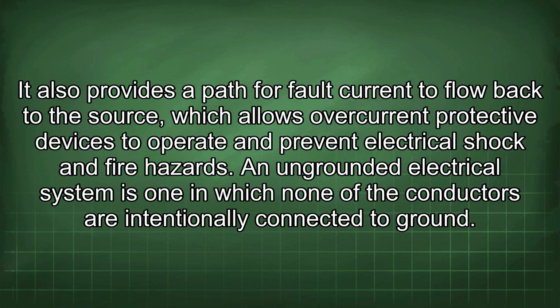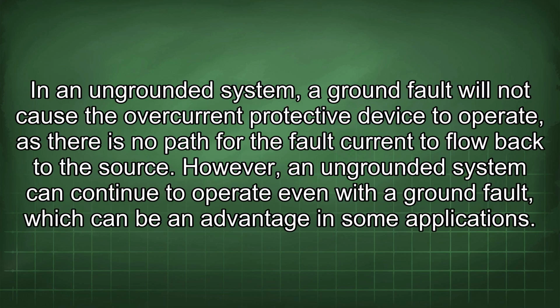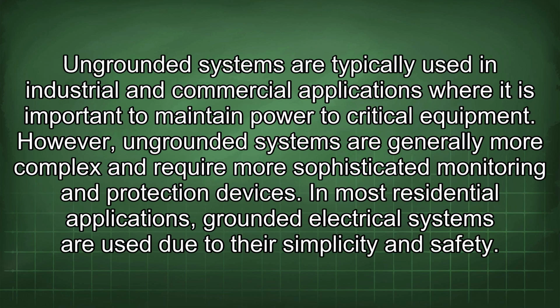An ungrounded electrical system is one in which none of the conductors are intentionally connected to ground. In an ungrounded system, a ground fault will not cause the overcurrent protective device to operate, as there is no path for the fault current to flow back to the source. However, an ungrounded system can continue to operate even with a ground fault, which can be an advantage in some applications. Ungrounded systems are typically used in industrial and commercial applications where it is important to maintain power to critical equipment. However, ungrounded systems are generally more complex and require more sophisticated monitoring and protection devices.